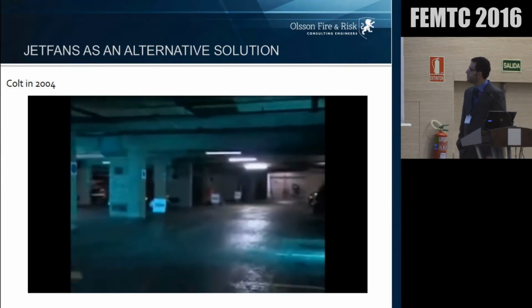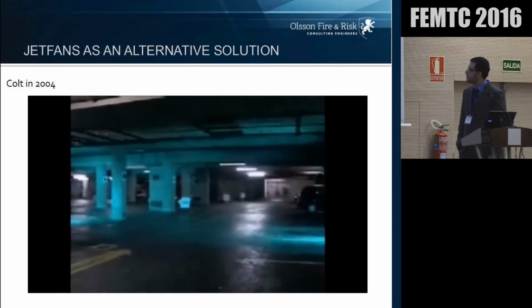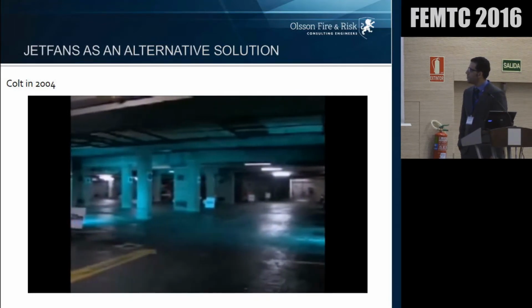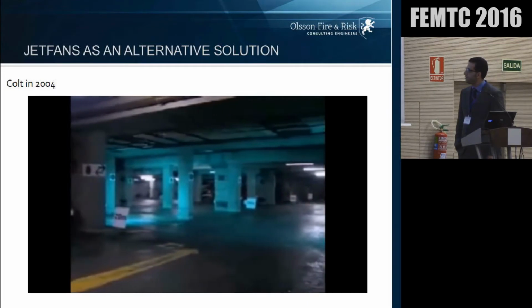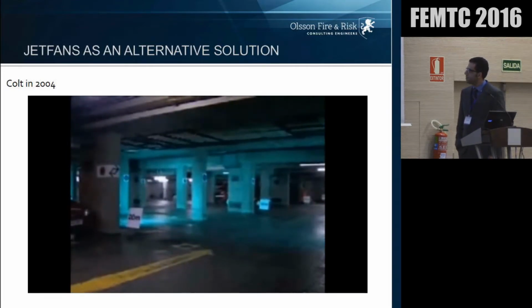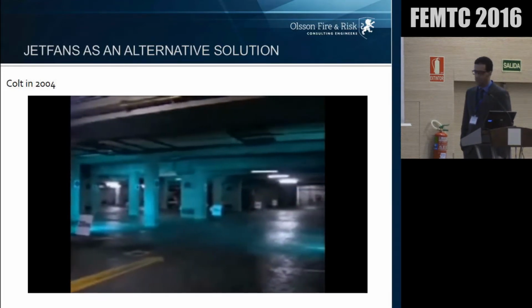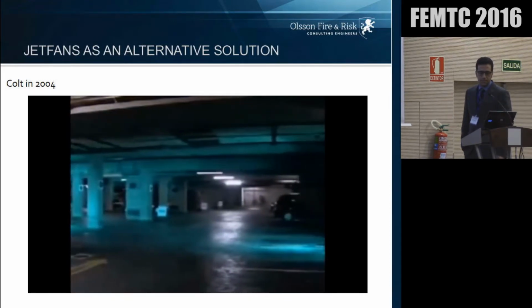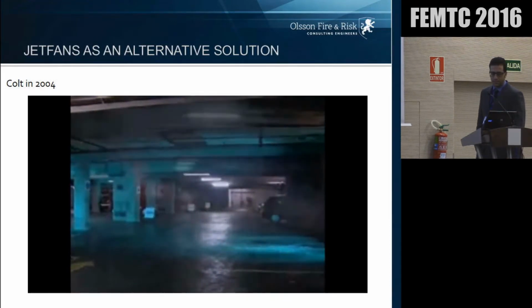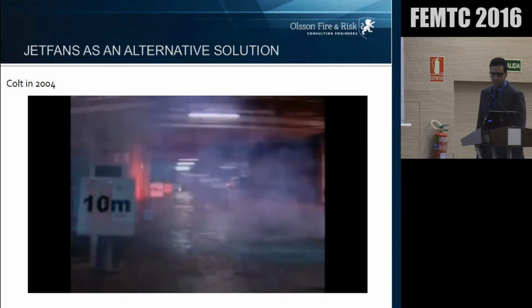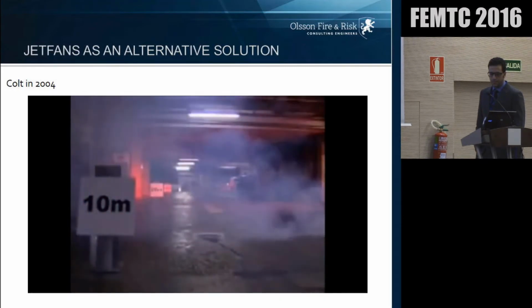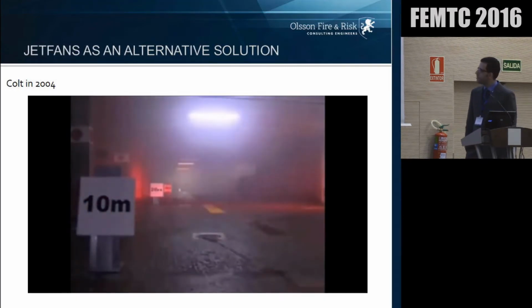The car park is a typical single-storey underground car park measuring approximately 50 metres long by 30 metres wide by 3 metres high. It's fitted with a traditional ducted extract system which provided 10 air changes per hour with extract grills at high and low level well distributed around the car park, as recommended in approved document B to the building regulations. The system has now been running for 20 minutes, and while visibility has improved, it is still poor, and the far end of the car park is not yet properly visible.